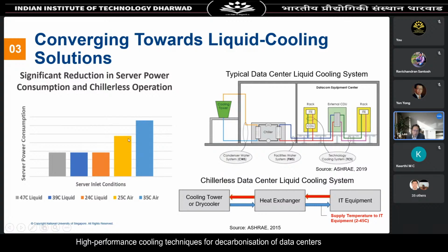So switching from air cooling to liquid cooling gives you, for example, a 30% reduction in server power consumption. But what is more interesting is that as you increase the supply temperature for liquid cooling, going from 24 to 39 to 47, you'll notice that the server power consumption actually stays more or less constant.